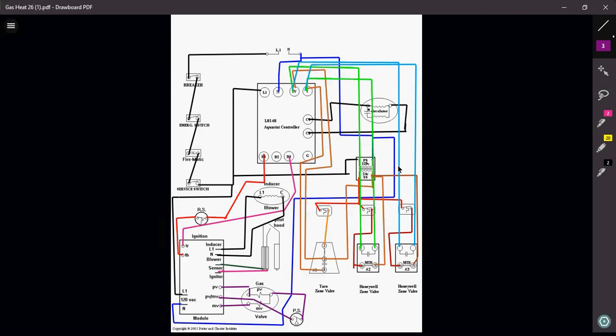And that is basically really how this whole thing operates. And in the event that the flame happens to roll out for whatever reason during the operation, that rollout switch will open and it will kill the ignition module, which will then in turn shut off your gas valve and all that stuff. And you won't have a call. And that's it.